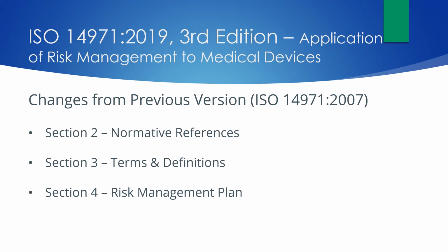Now we're going to discuss the changes from the previous version of the 14971 standard, which was published back in 2007. Section 2 was updated, and Section 2 is normative references. So normative references are an informative, mandatory element. A clause on normative references has been included to respect requirements in Clause 15 of the ISO IEC Directives, Part 2 of 2018. Section 3, Terms and Definitions, has been updated. Defined terms were updated, and some others have been introduced.